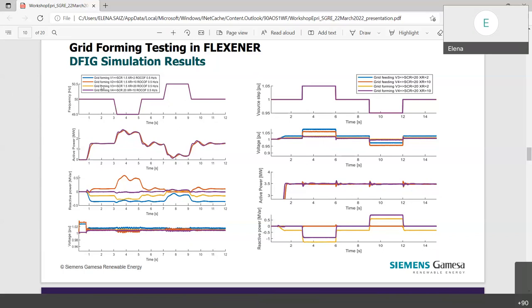Here, just as a sample, we provide simulations of our response, taking into account frequency deviation and also voltage deviation, comparing the results here with the grid feeding and here with different grid formings. The important thing is that, depending on what you want to obtain, you can parameterize the controller accordingly to obtain the inertia and the droop that you really want.